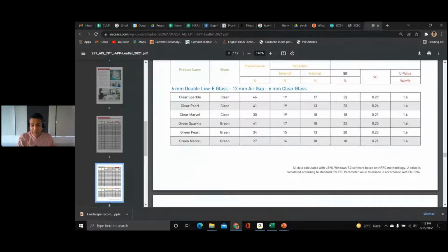Now we've selected 25, which is very stringent. Because when you look at the external shading factor, you can actually multiply it into the SHGC, which allows you to take a more relaxed glass. Why would you want to take a more relaxed glass?